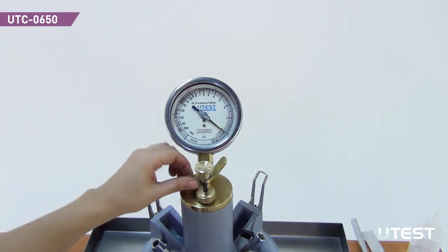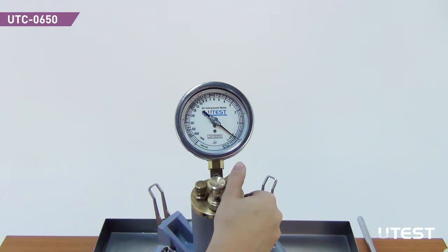If it does not show the initial pressure line after tapping, stabilize the gauge hand at the initial pressure line by pumping or bleeding of air. Press the main air valve latch.